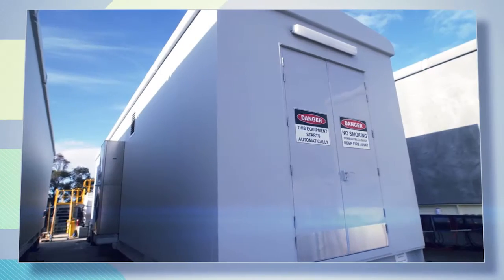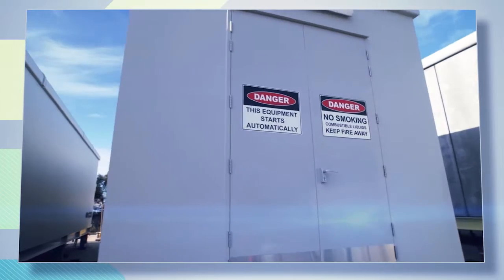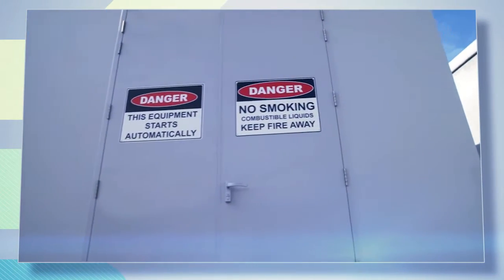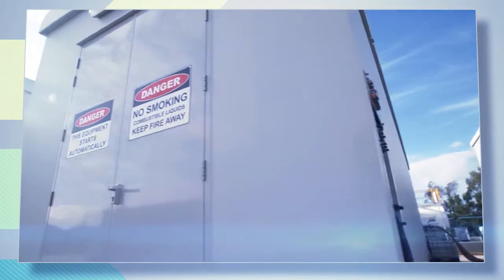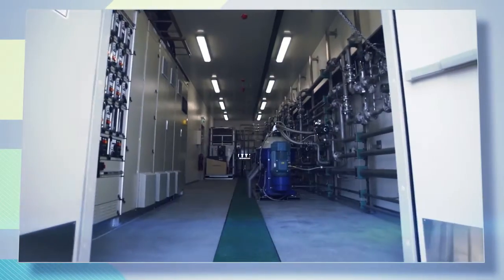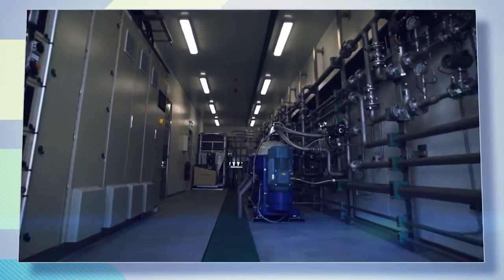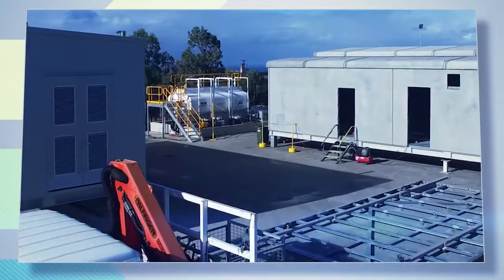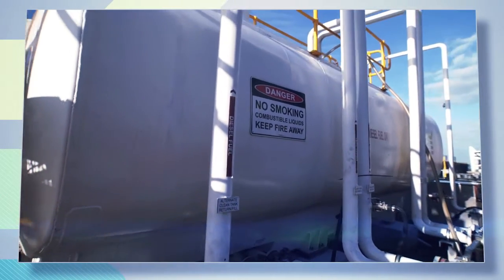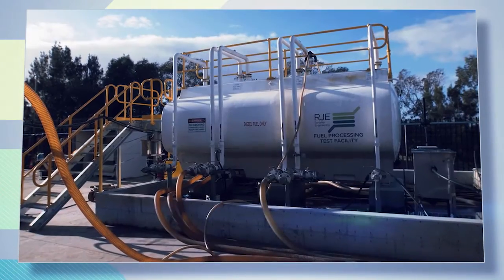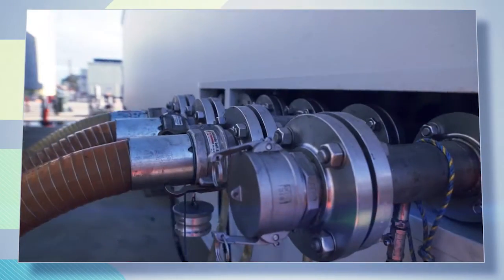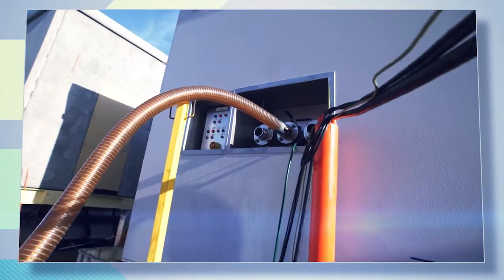The FuelBLOCK 50 is a liquid fuel processing and delivery system capable of supplying two 25 megawatt turbines or one 50 megawatt turbine. The module and all equipment are assembled at Lonsdale and fully commissioned before shipping to site. Once at site, the FuelBLOCK 50 is connected to prefabricated 85 kilolitre fuel tanks to provide a fast, complete solution for liquid fuel storage, processing and delivery.